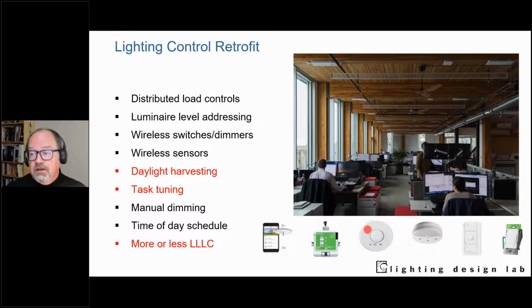So what we did was completely retool the lighting controls here. We added load controllers per each light fixture so they were effectively Luminaire level lighting control. Everything was individually addressed, though we didn't have the sensors in the fixture, so technically it wasn't true Luminaire level lighting control. We added wireless occupancy sensors, wireless daylight sensors, wireless switches throughout the space, and a communication hub.